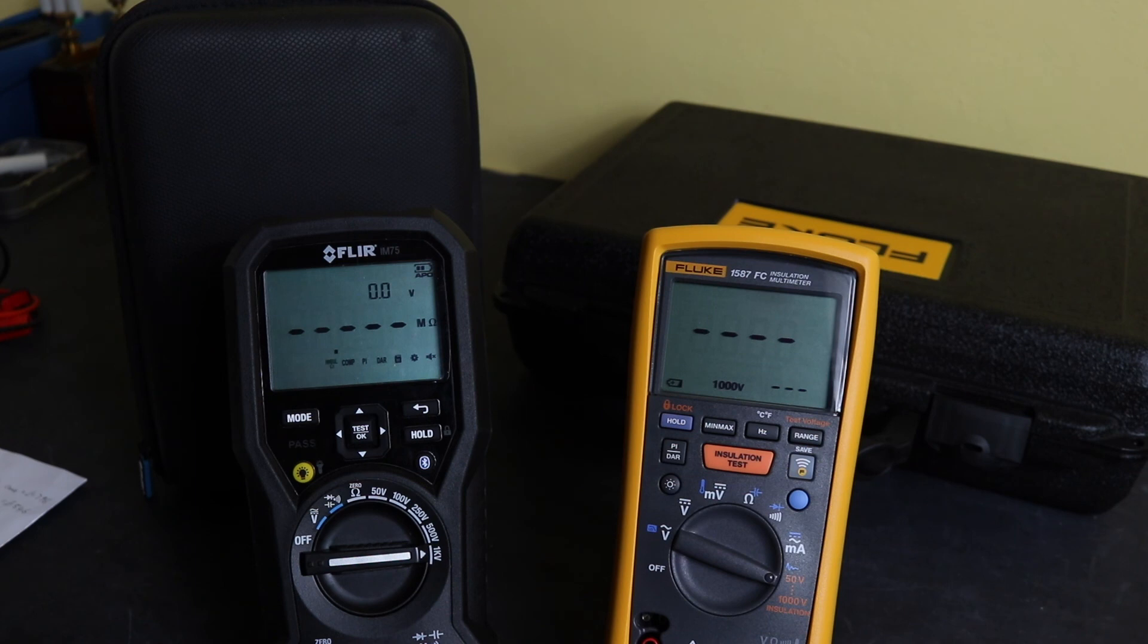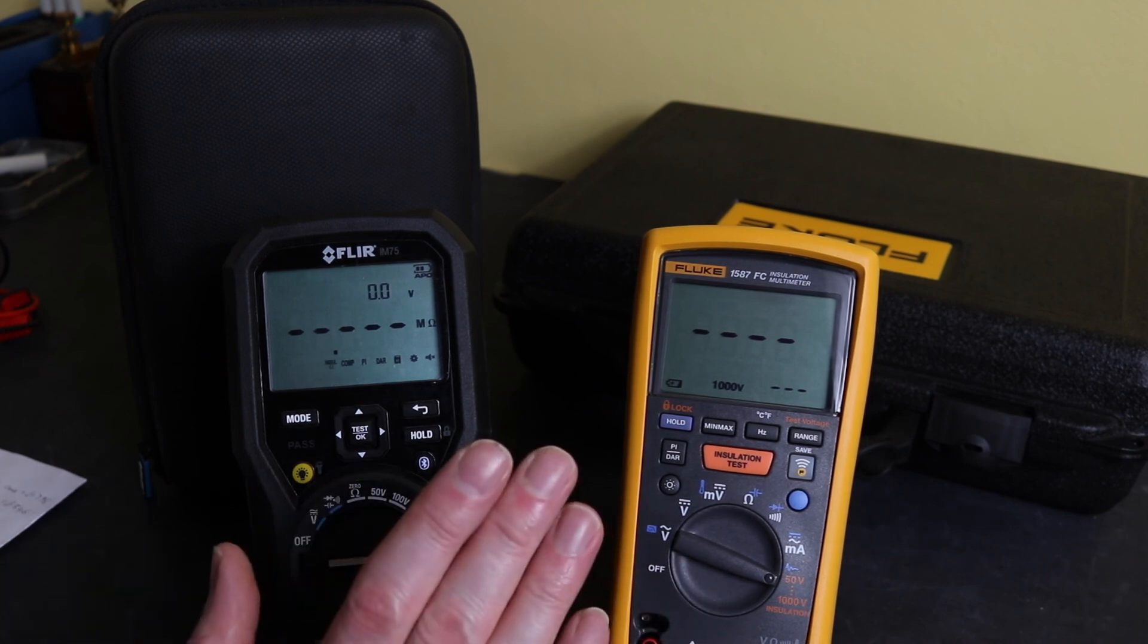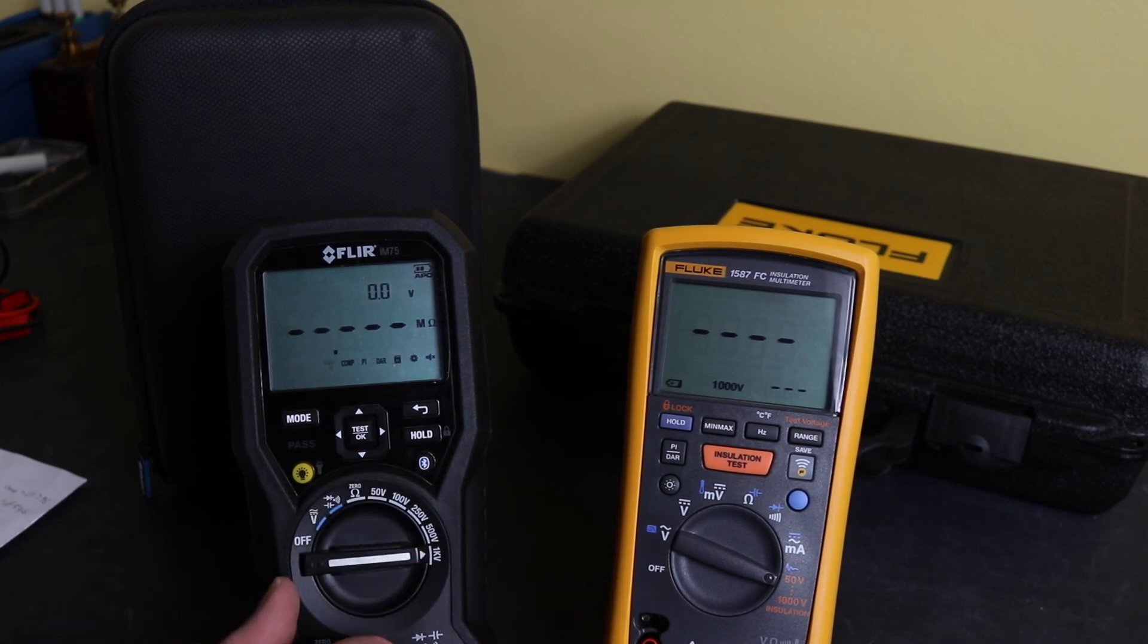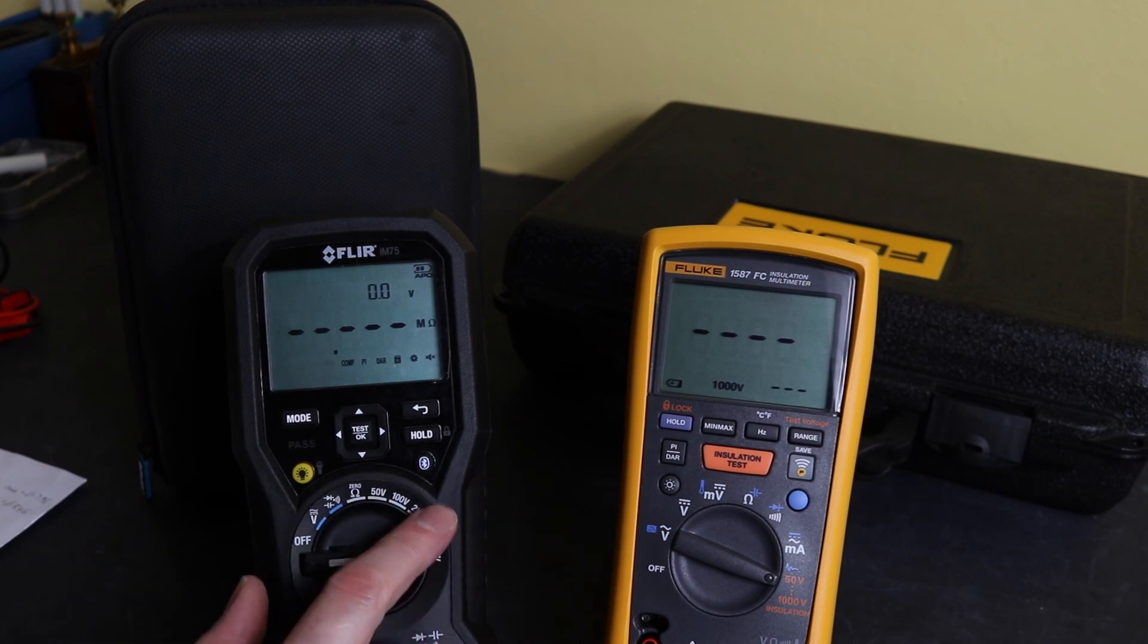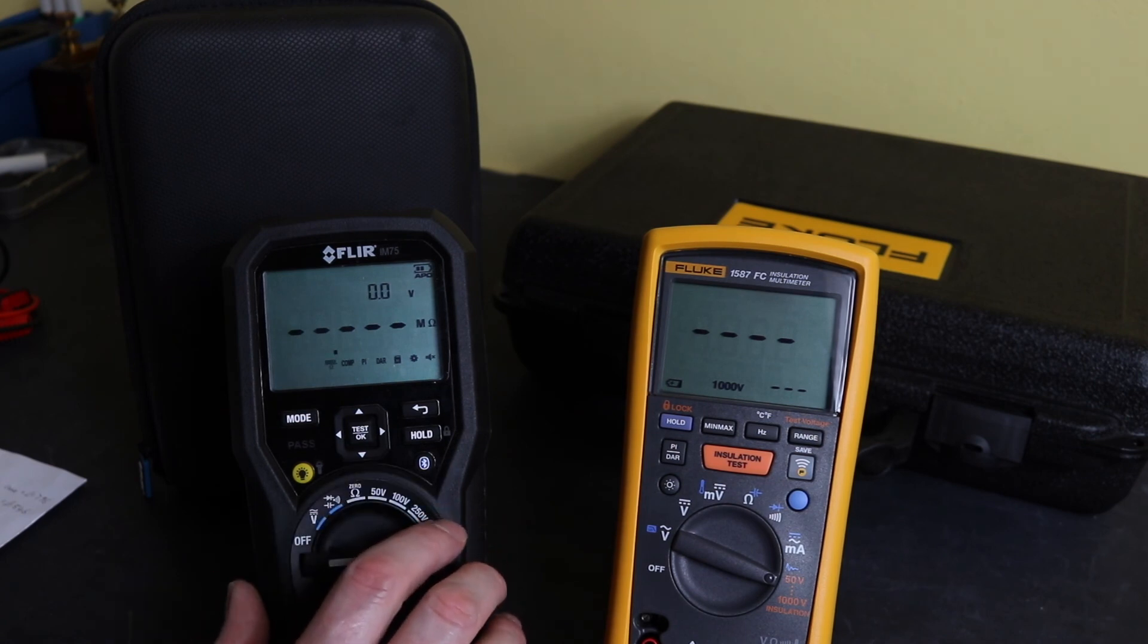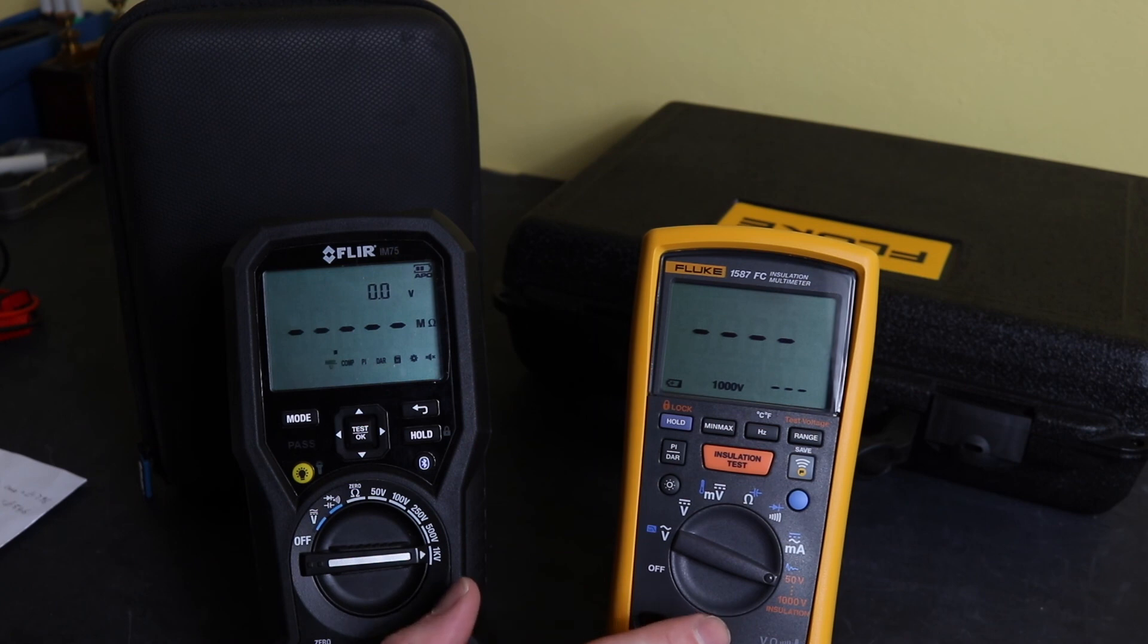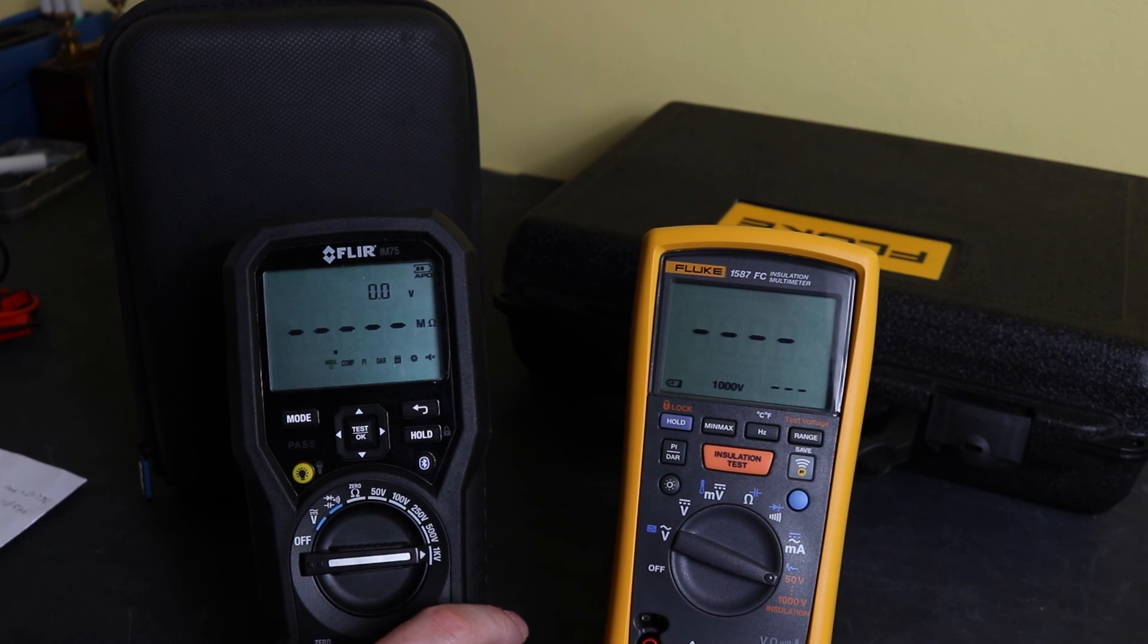In terms of preference for myself and for my particular work that I do, as a general instrument I would probably prefer the Fluke over the Flir unit. I'm not sure if the software that comes along may change my opinion of that, if that gives me more testing capabilities. But really this Flir I use it predominantly for specific testing using the MeterLink function. In terms of every other test really, to be honest, the Fluke will match the Flir. Neither of the instruments are particularly good for insulation testing in terms of PI functionality.